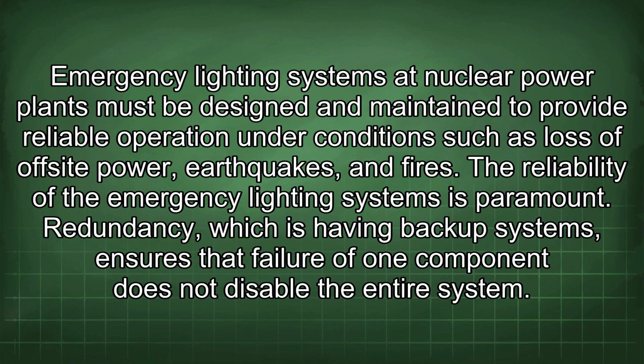Emergency lighting systems at nuclear power plants must be designed and maintained to provide reliable operation under conditions such as loss of off-site power, earthquakes, and fires. The reliability of the emergency lighting systems is paramount. Redundancy, which is having backup systems, ensures that failure of one component does not disable the entire system.